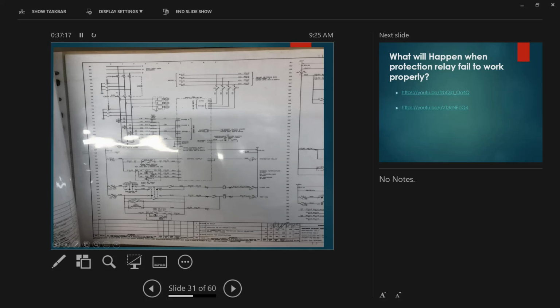Sometimes the experienced guys, Janelle and the rest of the guys here, if there is no drawing, only look at the terminal numbers. From the terminal number here, C11, we can trace that back on the CT link as C11. That's where I'm going to connect my red phase. White, red, white, blue. So normally we can identify it, but it's better as well to have the proper drawing as much as we can.